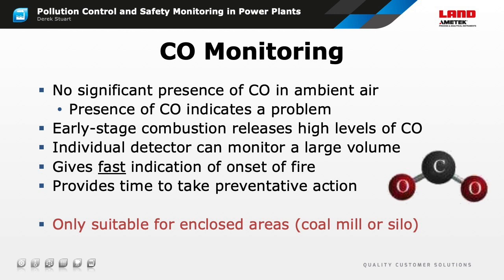Choosing an appropriate alarm level for the CO sensor is also important. A low alarm threshold gives the earliest warning of a problem, but it can result in nuisance alarms. An excessively high threshold will allow spontaneous heating to progress to the point of being hazardous without giving an alarm. The exact value is specific to the fuel type and to the storage location, but in many cases a value between 100 and 200 ppm works well.